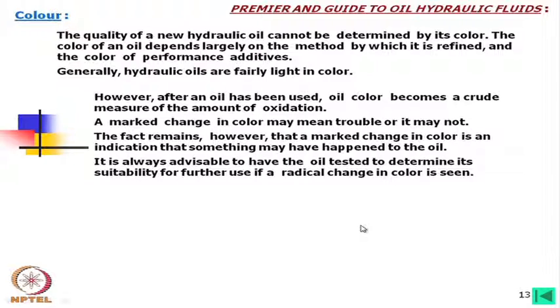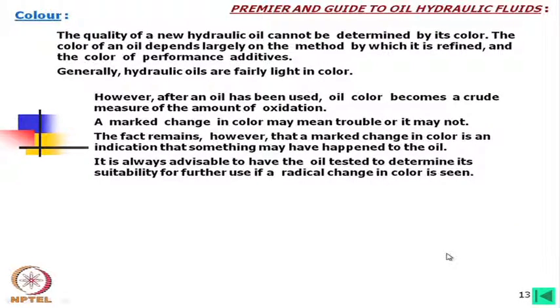A radical change in color — for example, the oil becoming very dark suddenly after a few days — may indicate failure in the oil or excessive friction or burning at some point in a component. This gives an indication that something is wrong in the system, not just in the oil. Developing the expertise to guess the problem from oil color is a valuable skill.